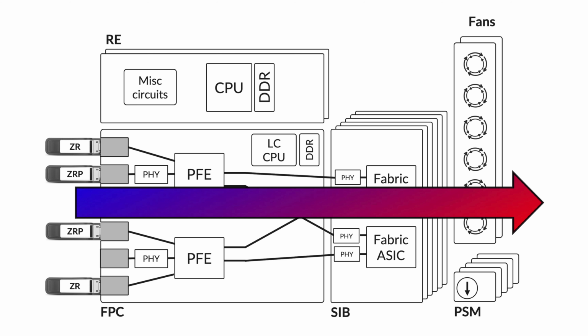It's important to treat high power optics as a specific case. Indeed, they will preheat significantly the airflow entering the router, and we have seen earlier that it has an important impact on the leakage power of all internal components. Consequently, when you measure the power used by a system, you cannot execute a test in your lab with a router just wired with DAC or AOC interfaces, and then add up the power used by your high power optics, like 22 or 25 watts per port. It will not be an accurate estimation, because with low power optics, the internal temperature of the chassis will be much lower, and consequently, the leakage power will be lower. So you will need to execute a very specific case with high power optics to be realistic.